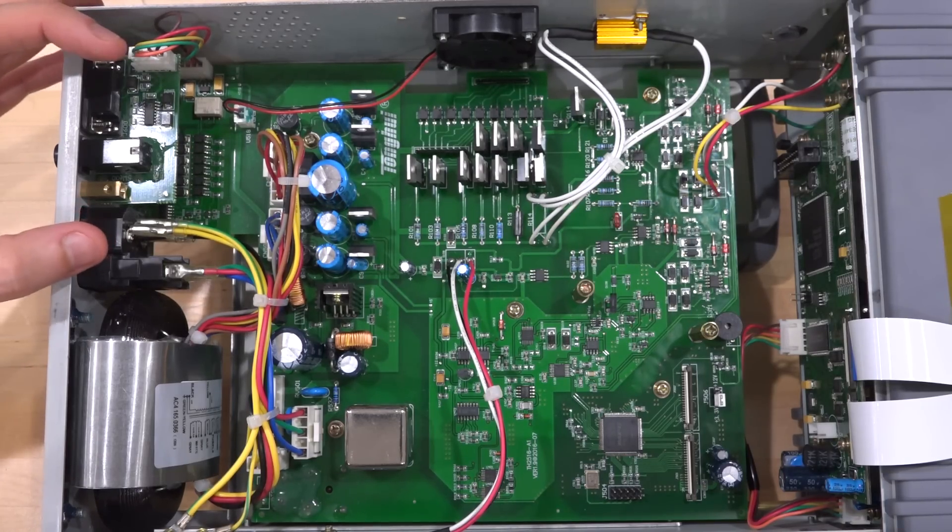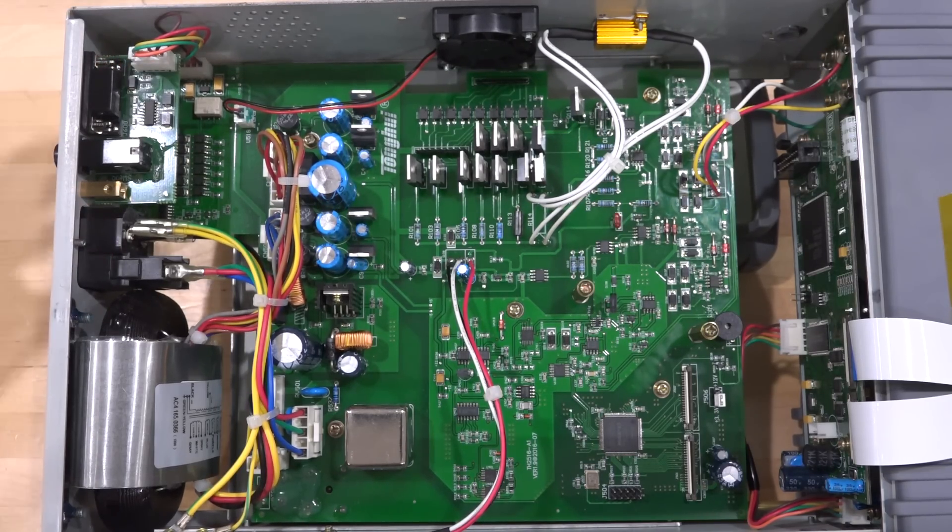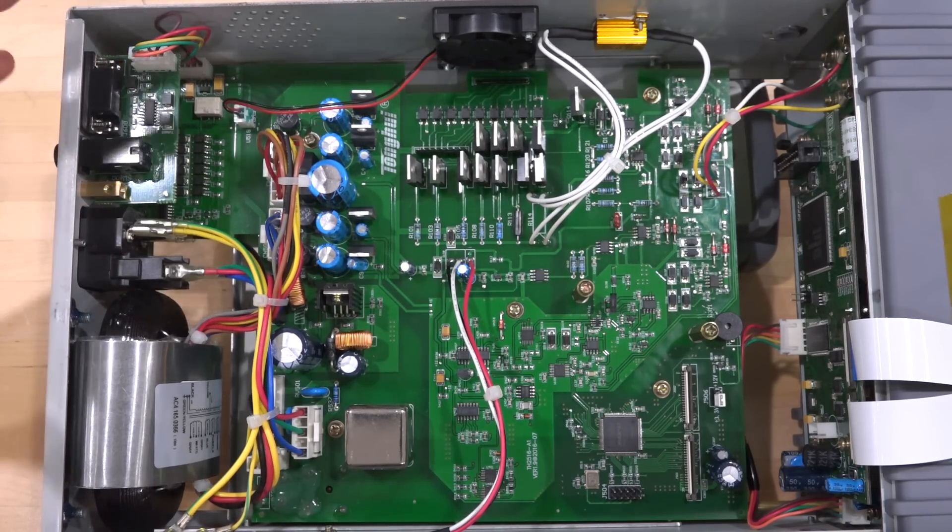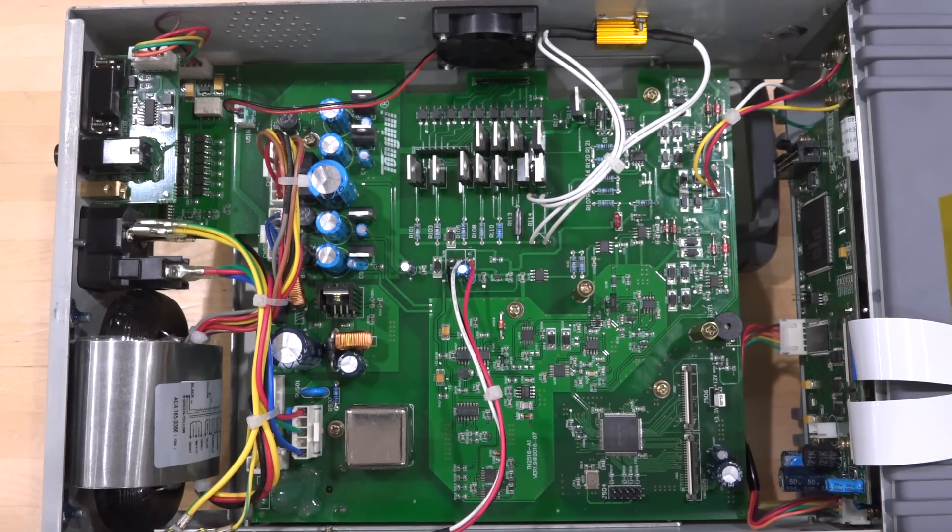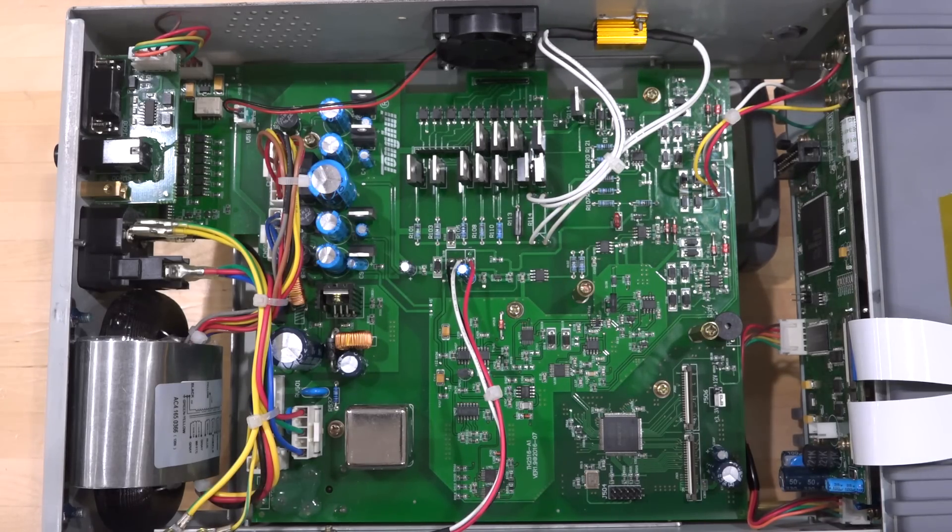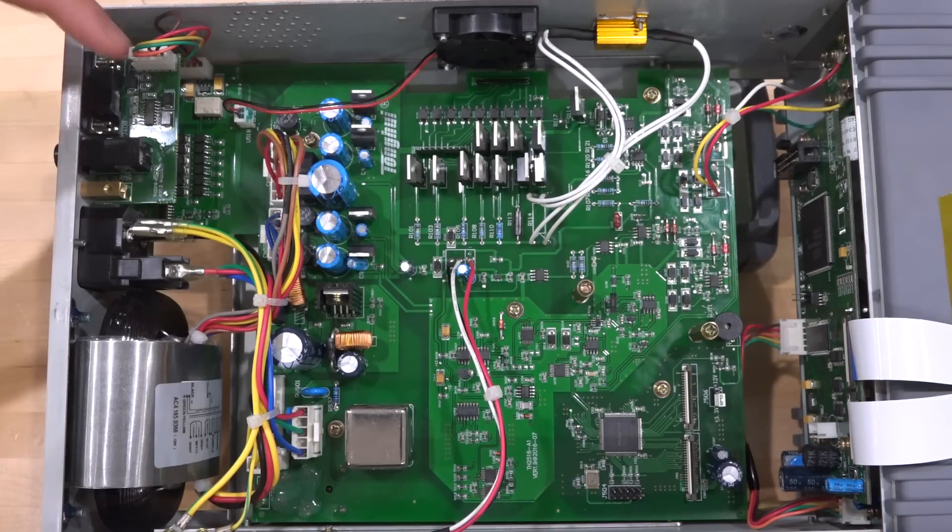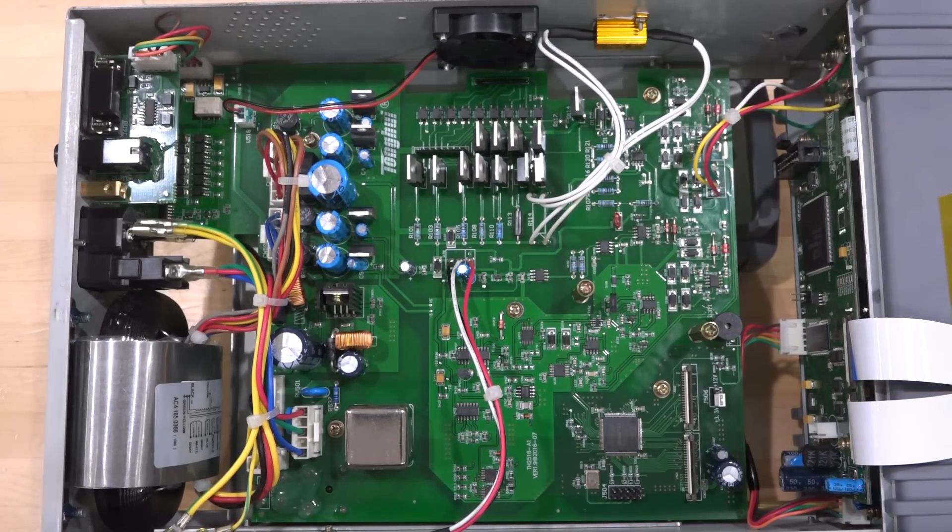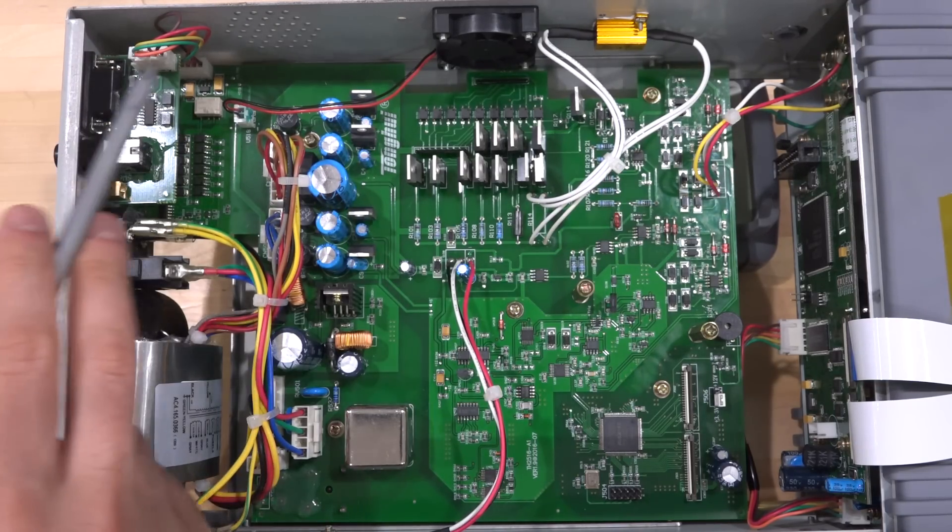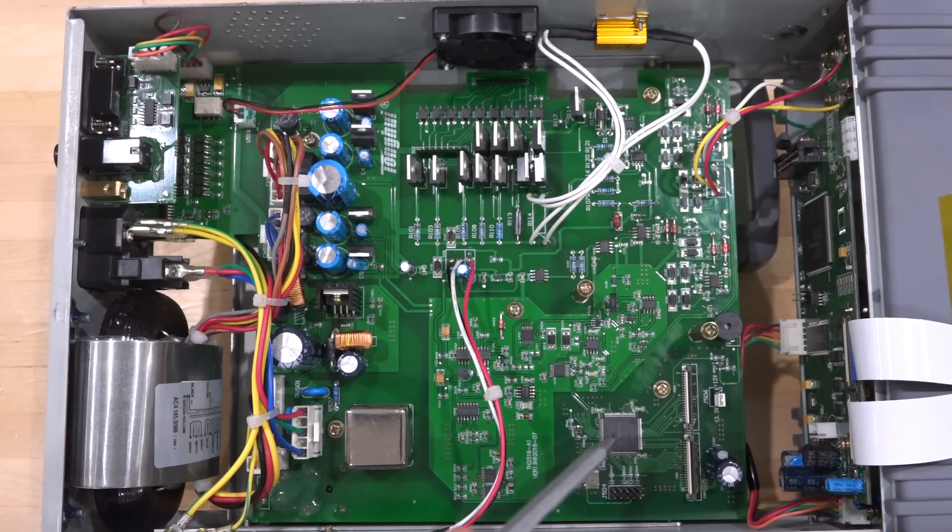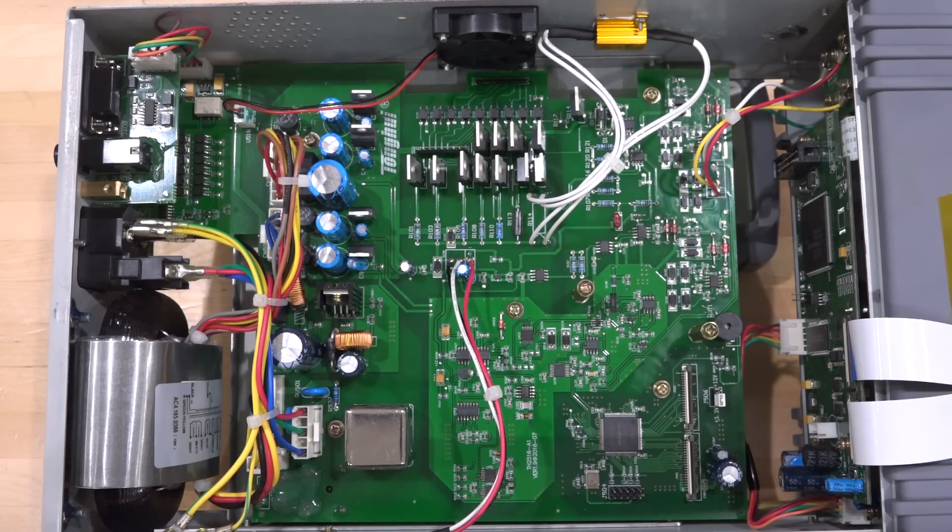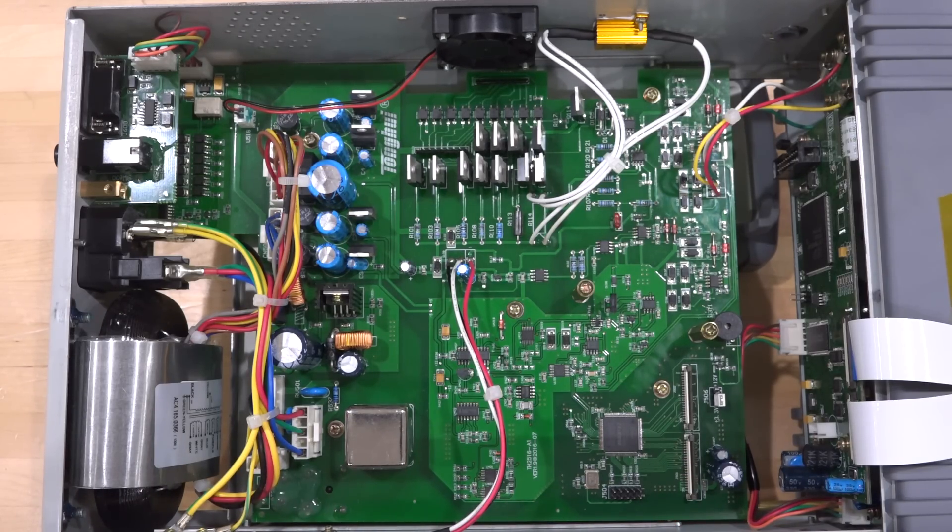Everything else is really pretty self-explanatory, nothing unusual going on. We do have a temperature sensor interface in the back which you can plug in and that compensates for the temperature measurements and you're going to get a reference temperature of what's going on from outside. There's a serial and USB port in the back as well which has to be routed all the way onto this FPGA and then ultimately into that board.